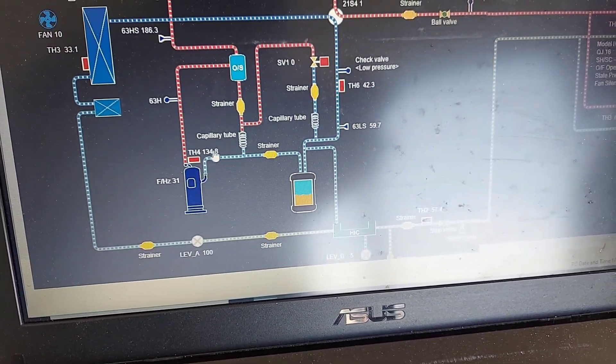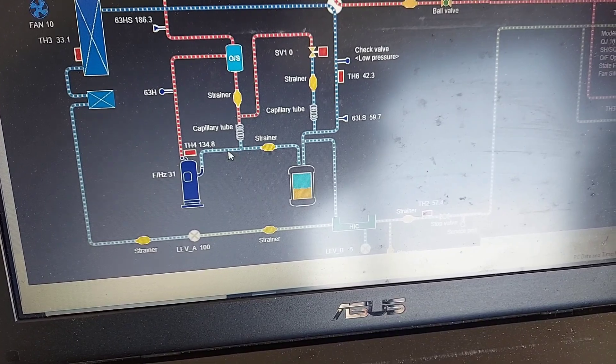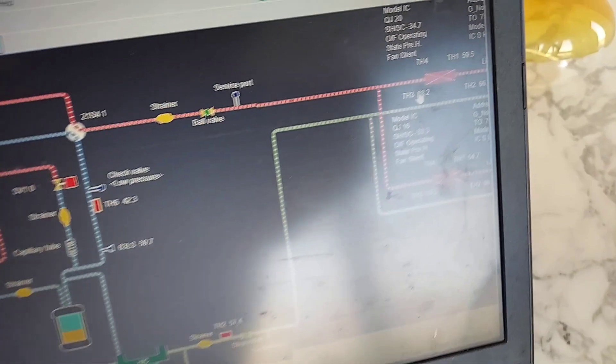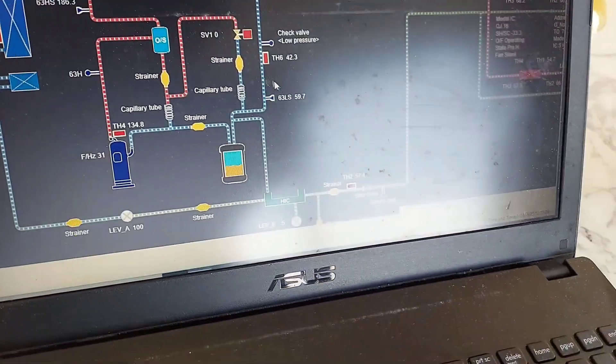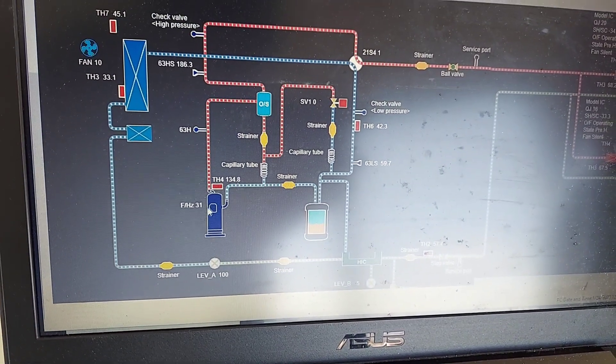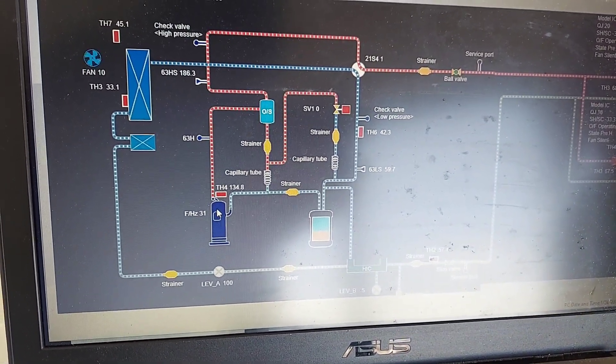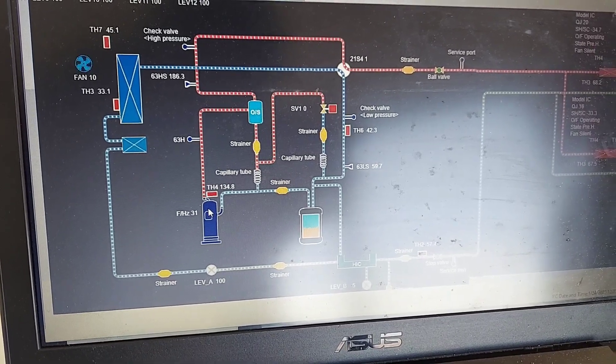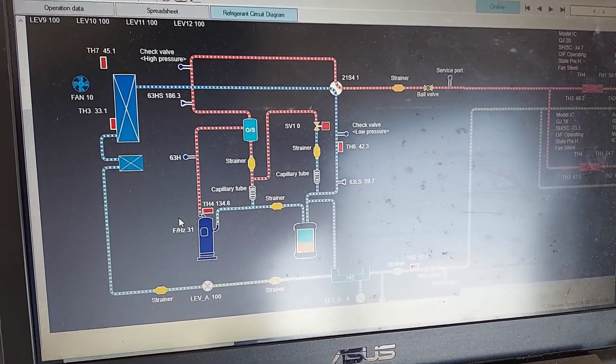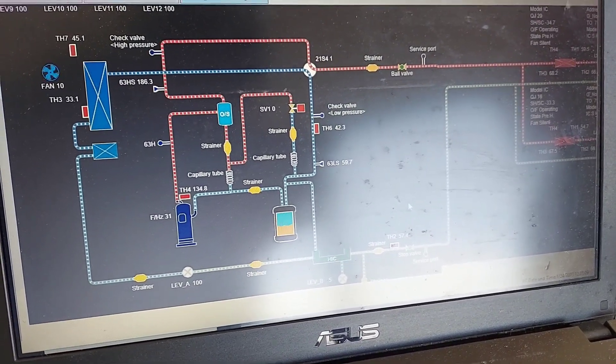And this discharge thermistor is rather hot even though we are 68 degrees over here. You know, so yeah, on the looks of this I could tell you already that it's not looking too good. We're going to have to get some refrigerant in the system. But I'm going to let it run for 10 more minutes and then I get a better look at the system.